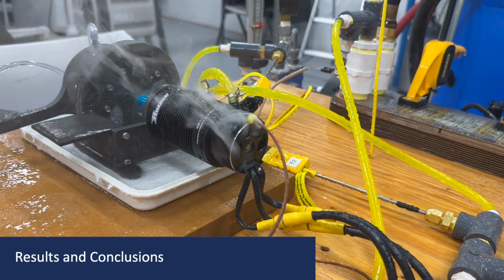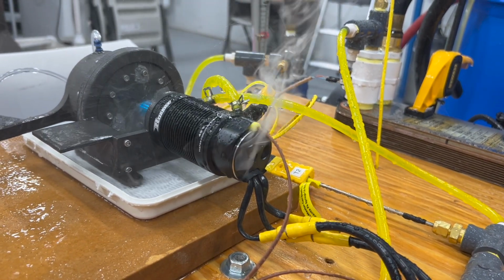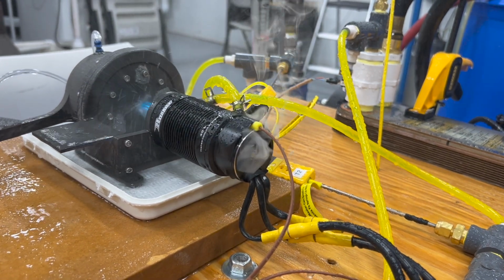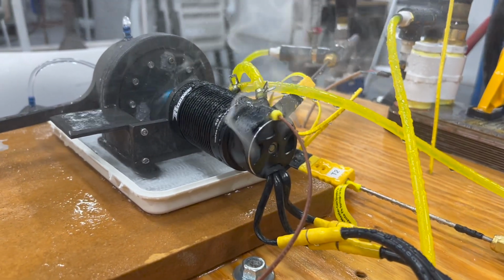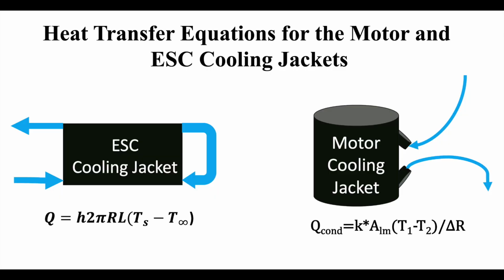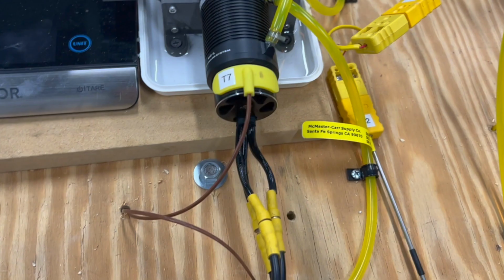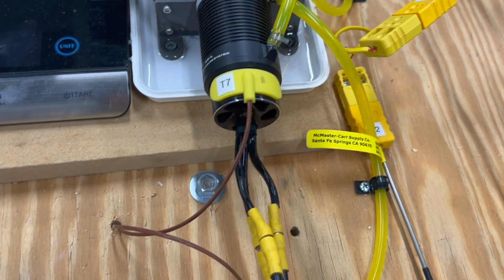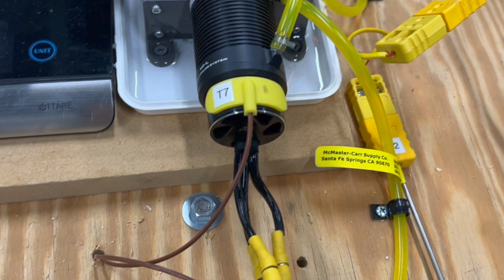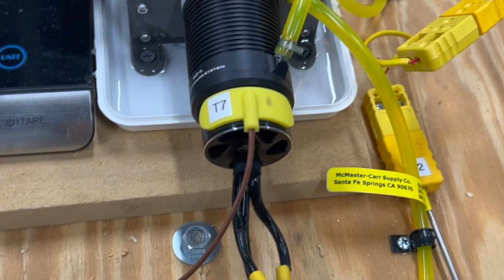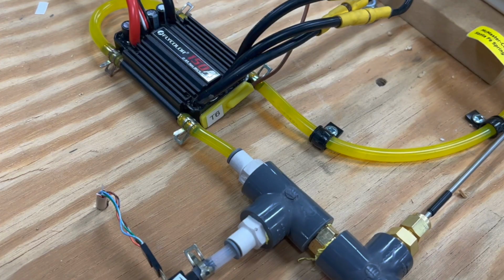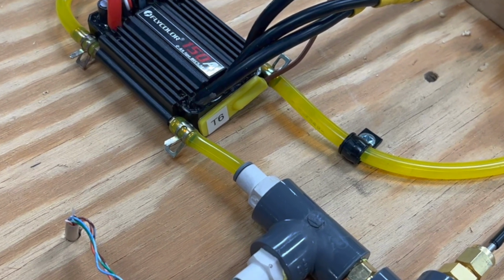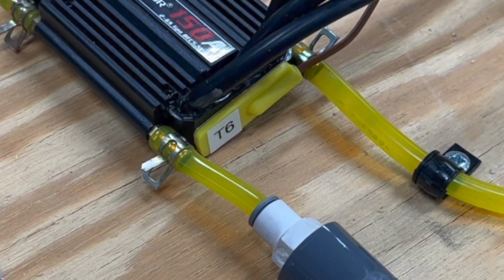When running the experiments, it was determined that no amount of cooling water was sufficient to keep the motor and ESC cool. Running at 1.5 gallons per minute of cooling water and 50 amps, the electronics reached 45 degrees Celsius. However, the cooling water increased by less than 1 degree Celsius, meaning very little heat transfer occurred between the electronics and the cooling water. After running for 3 minutes, the motor started smoking and the experiment was stopped. Since the temperature sensors are on the outside of the electronics, we suspect the internal temperatures were much higher and above the operating limits. It can be concluded that inefficiencies in the cooling jackets of the motor and ESC are the limiting variables, and insufficient cooling water flow rate is not the cause of motor and ESC burnout.